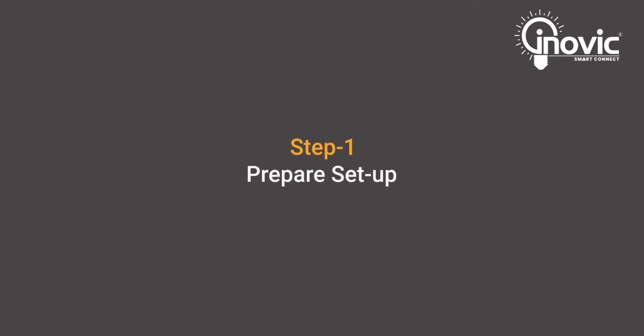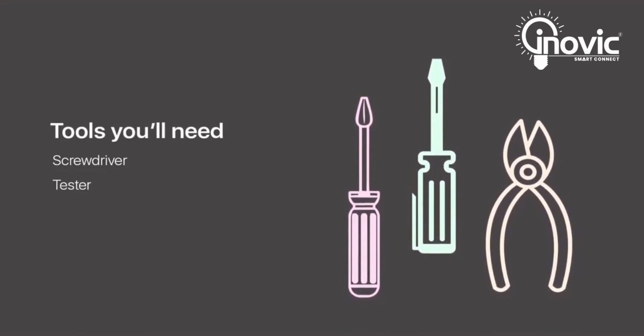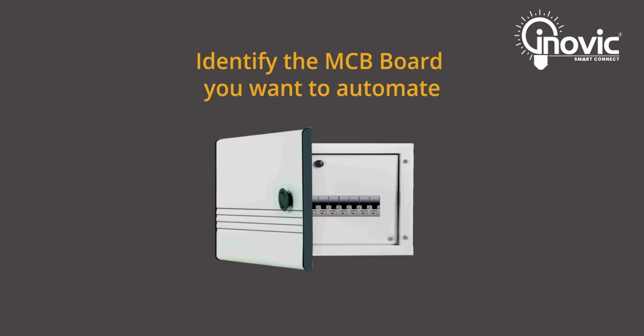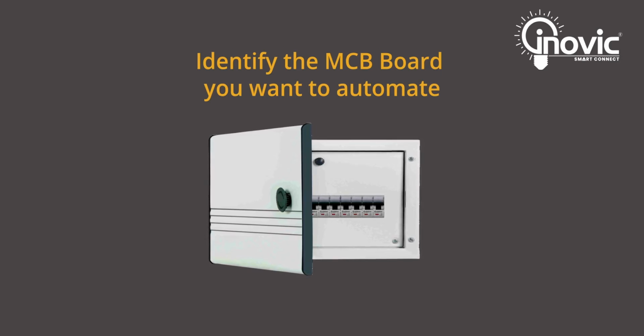Step 1. Get ready to install. Collect all the tools required for the installation. For this, you will need a screwdriver, tester and pliers. Now identify the MCB board you want to automate with the Smart MCB. Also, make sure that you have a neutral wire inside the switchboard. A neutral connection is mandatory for the Smart MCB.